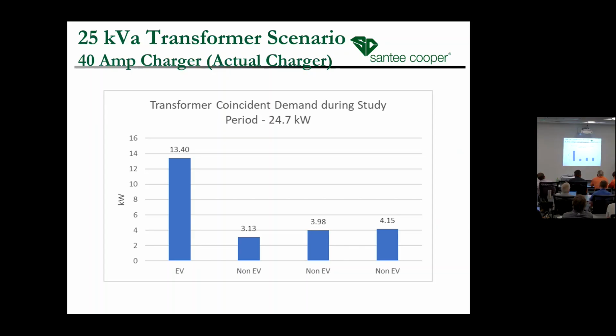So right now we're just in a monitoring scenario, but if we were to see something serious—say this peak was 35 kW or something like that—I think we'd take a deeper look and ask how often this is happening. Was this a one-time thing that never happened again on this transformer, or is it happening three times a week? And if it's happening three times a week, maybe those guys go out and look at changing that transformer out for a 50 kVA to combat the issues there.